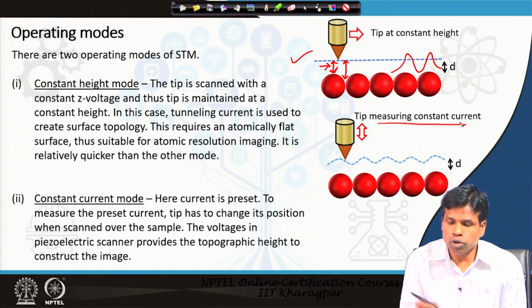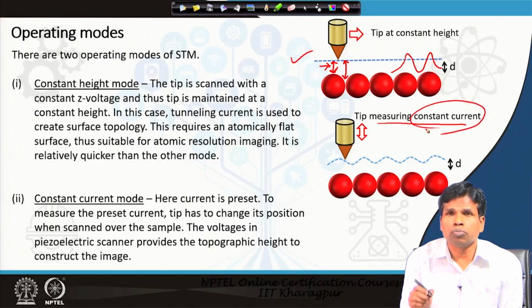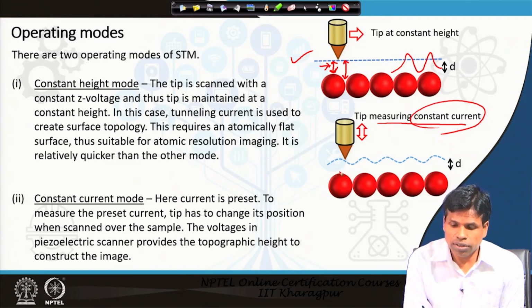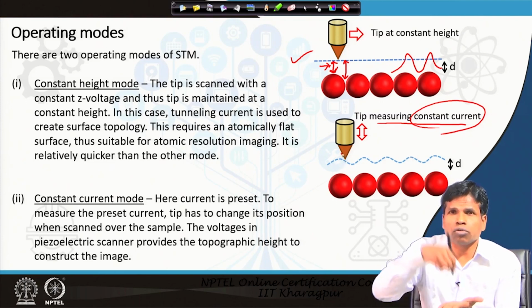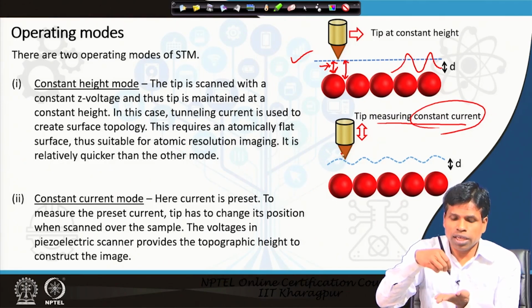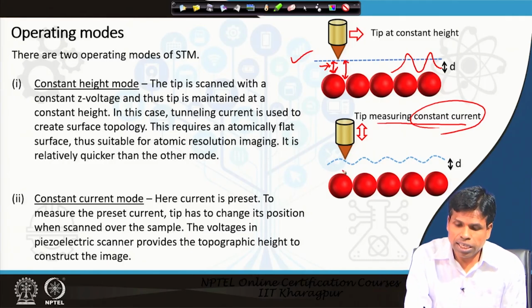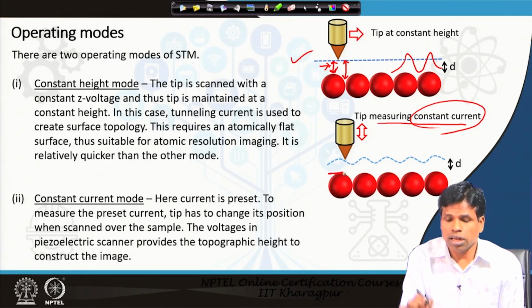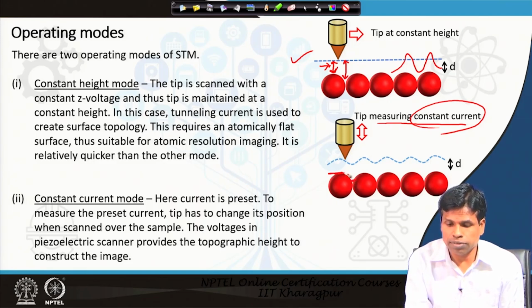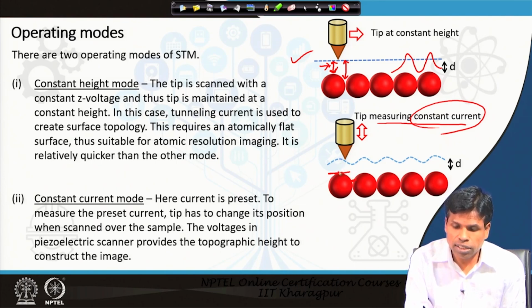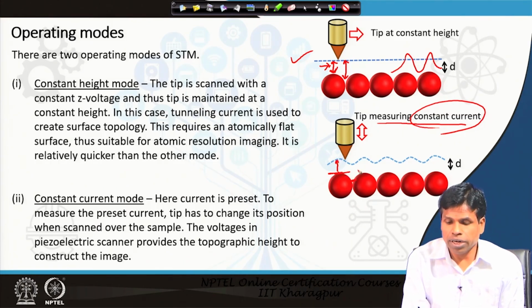So here, our feedback control will set a preset current that it wants to measure only. In order to do that, as you see here, we want to measure a constant current. My tip has to go up and down to see that preset current. If at some places the sample is a little above this place, then in order to measure constant current, the tip has to go a little upward here.